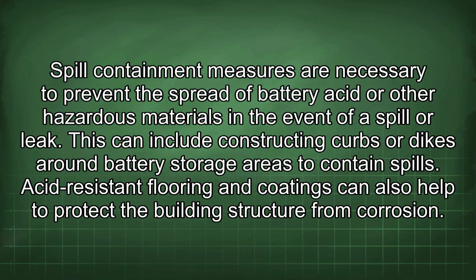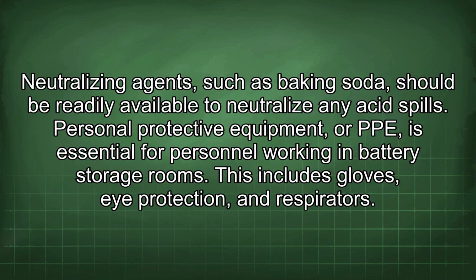Spill containment measures are necessary to prevent the spread of battery acid or other hazardous materials in the event of a spill or leak. This can include constructing curbs or dikes around battery storage areas to contain spills. Acid-resistant flooring and coatings can also help to protect the building structure from corrosion. Neutralizing agents, such as baking soda, should be readily available to neutralize any acid spills.